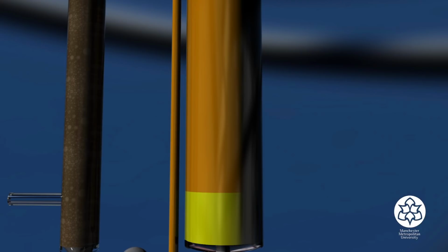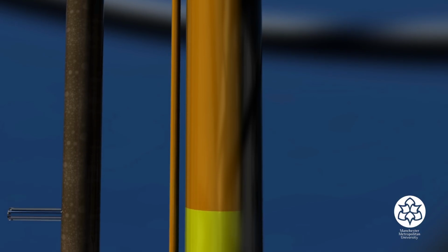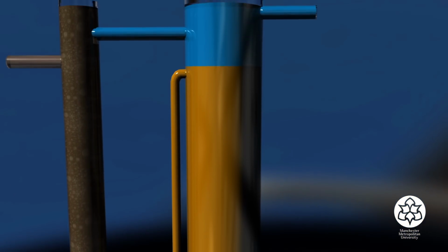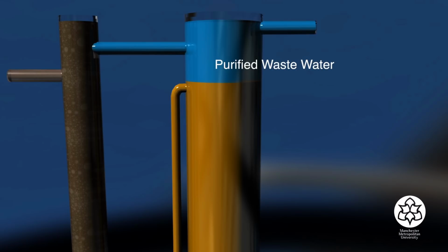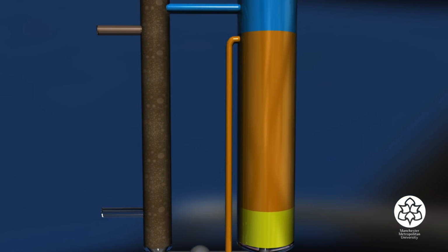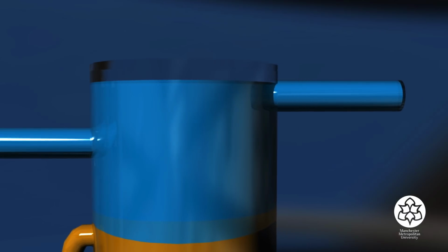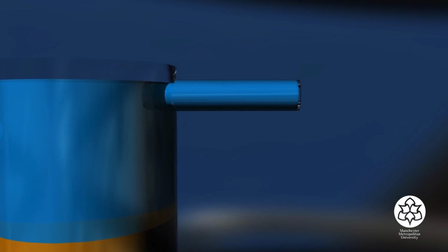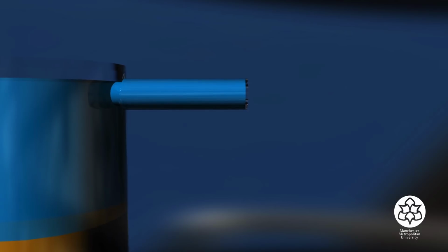Microorganisms grow on these porous carbon particles to form a biofilm, and that biofilm gives us our biological activity to purify the wastewater. As the bed expands, it continues to fill an increased volume of the expanded bed until it reaches the bioparticle overflow line, where it is drawn automatically back down to the base of the bed and is re-injected. Treated wastewater leaves the top of the bed and goes off to be discharged.